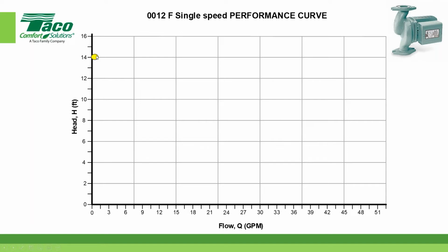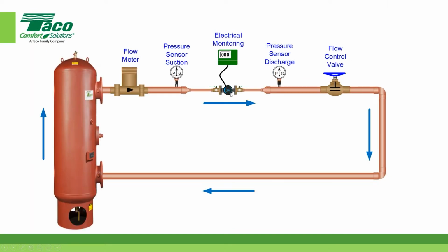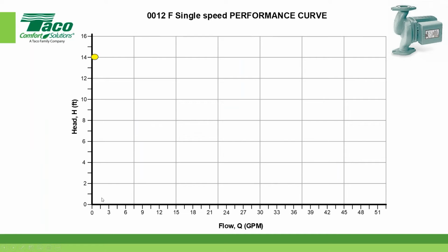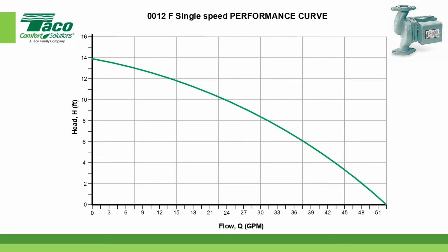And then, of course, electronically, we would make a mark right here. Then we go back to this thing, we shut the pump off, and now we open this valve all the way up, and we turn it back on. And now what are we looking for? 0 resistance. How much flow does this thing have? And of course, we'll make a mark there as well. Then we'll go back and close that valve off a little bit, and make another mark, and close it again and again and some more, and we'll eventually get the ability to actually draw in the blanks, and that's how we get a circulator performance curve.